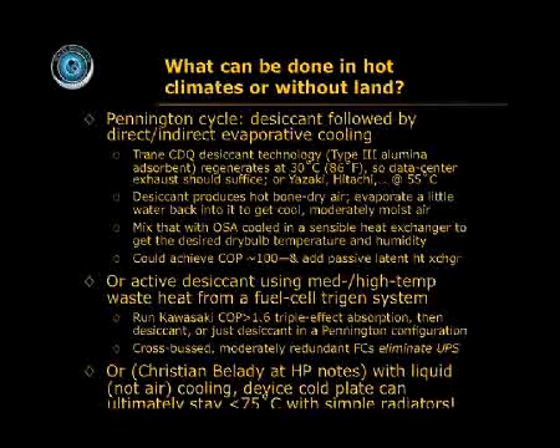Now, you could, of course, go to a trigeneration system with an advanced engine or microturbine or a fuel cell. And then you have medium to high temperature waste heat. So you could, for example, stack it with absorption on top. You could use a Kawasaki over 1.6 COP triple effect on top of the cycle, then a desiccant under that. Or you could run all desiccant. And, of course, if you have a number of fuel cells that are cross-bussed and moderately redundant, you can eliminate your uninterruptible power supply and its costs and losses.